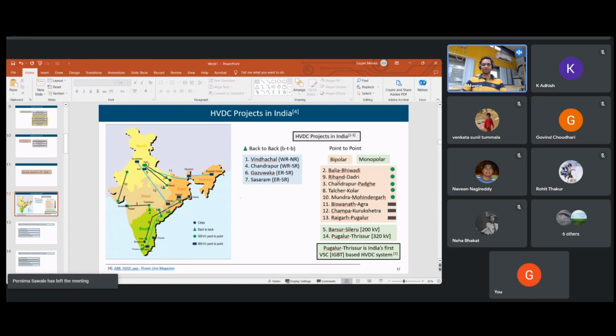Between these two, bipolar is best. So we can see all these lines are bipolar. This is the first line, so it was monopolar because at that time it was the initial stage of HVDC. Similarly, because it is our first VSC project, monopolar is economical and simple, and to begin with a technology, we start with monopolar. And in future, we can see bipolar also.